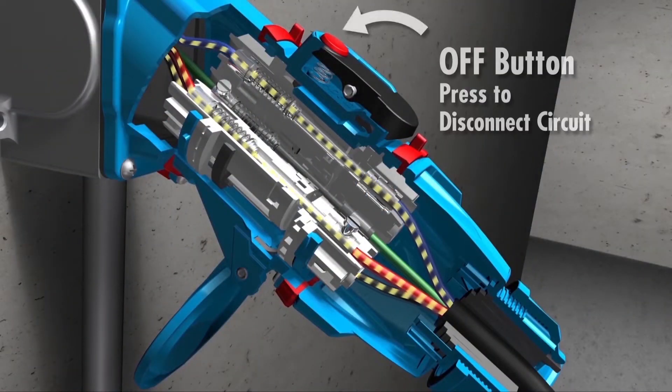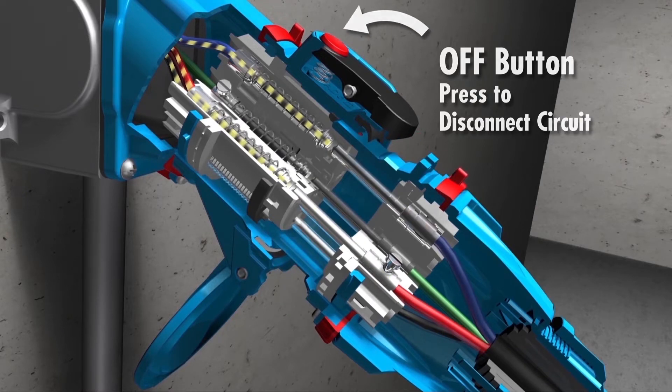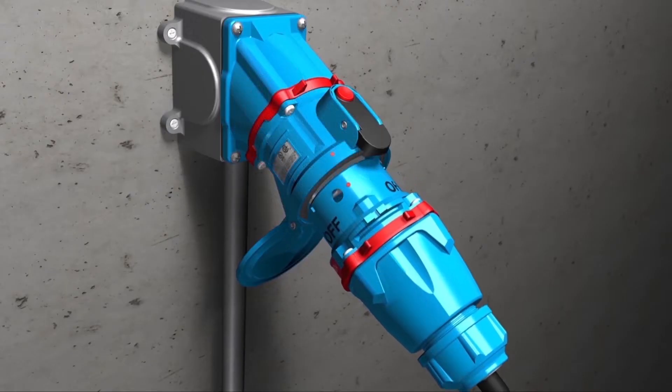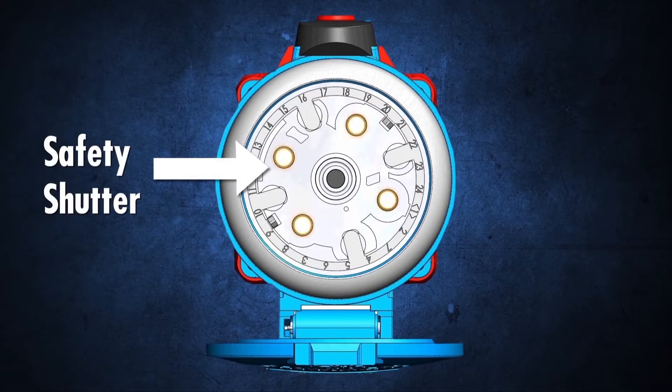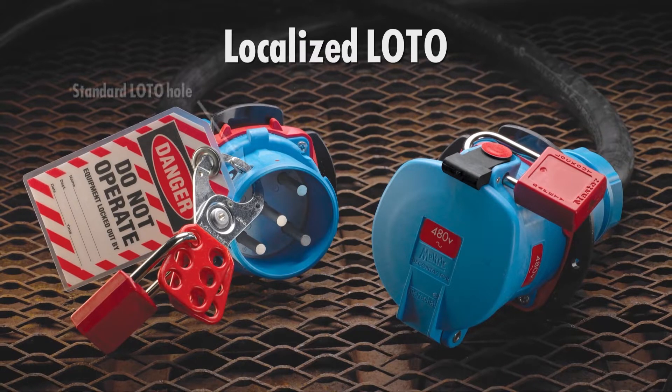An integral switch mechanism inside the receptacle safely de-energizes the plug before an operator can withdraw it. Once the plug is removed, a safety shutter shields the operator from live parts, and the plug can be easily locked out.